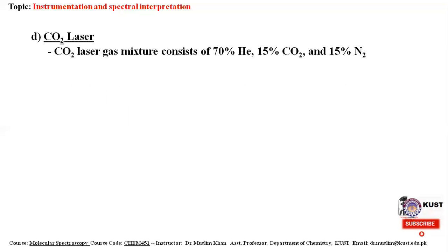The next one is the carbon dioxide laser. The carbon dioxide laser uses a mixture of 70% helium, 15% carbon dioxide, and 15% nitrogen.